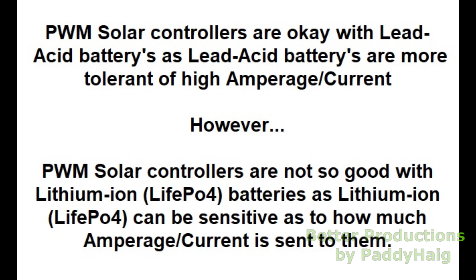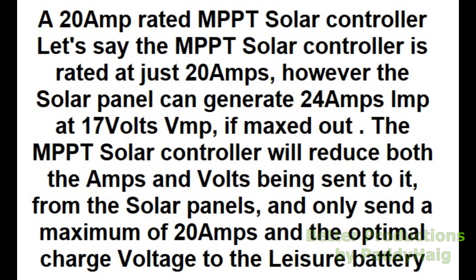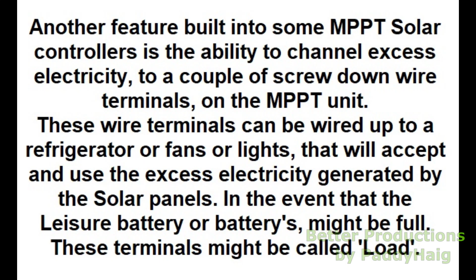If the sunlight is at its maximum and the solar panel is creating 400 watts, or 24 amps at 17 volts, then the MPPT controller will regulate and pull down the amperage to the desired 20 amps or less. An MPPT controller computes and monitors the leisure battery's voltage needs, and also limits the amperage to the best rate to charge the battery, regardless of the battery's chemistry, using the most ideal charging formula or profile for the specified battery. Any excess power that cannot be sent to the battery will be safely discharged by the MPPT controller, usually as moderate heat through a metal heatsink built into its body, or by a fan built into the controller discharging generated heat.